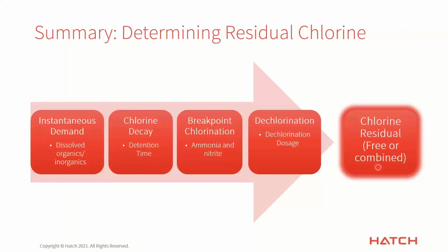All right, so now I'm just going to do a very quick summary of the steps taken by the model to determine residual chlorine, and also just remind you of the key factors that affect the residual at each step. The first one is the instantaneous demand, and this is affected by the dissolved organics and inorganics. The second one is the chlorine decay, and this is affected by the detention time.